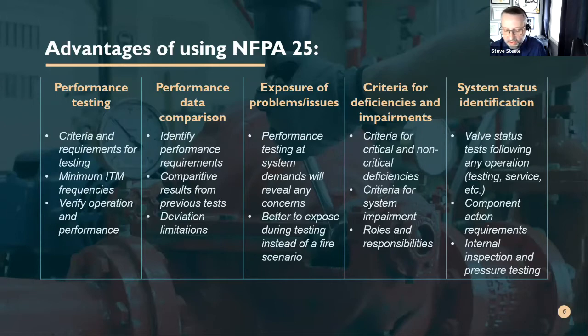So the main difference between 25 and the OFC, again, the OFC from its inception: NFPA 25 is based on performance, and is more analytical, if you will, more comparative. It's not a verification, it's not a validation or a checklist. Even when you get into the report, the reporting of an inspection and test on an annual basis for some of these systems, it shouldn't necessarily be a checkbox that something was looked at or operated. You're going to see that when you look at some of these inspection reports. It's a matter of how things were conducted, what was done, and what the results were.